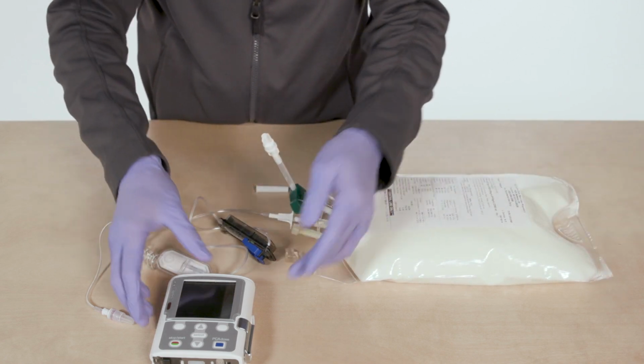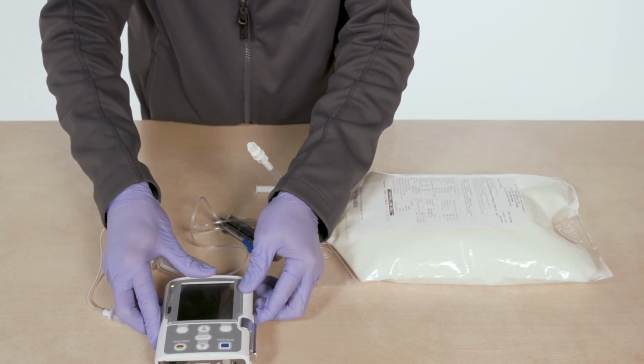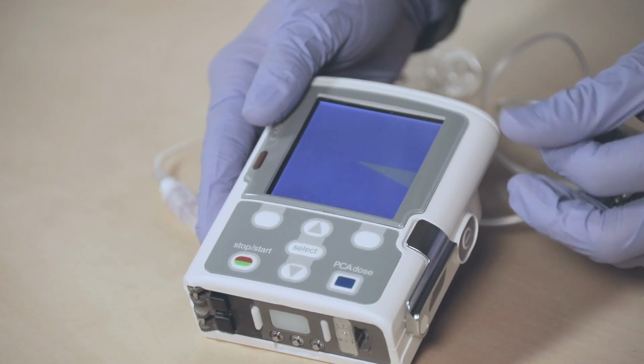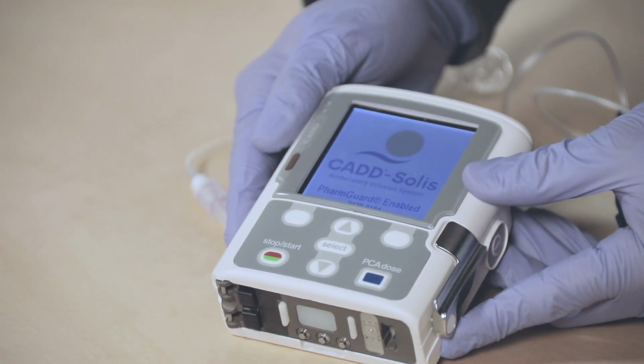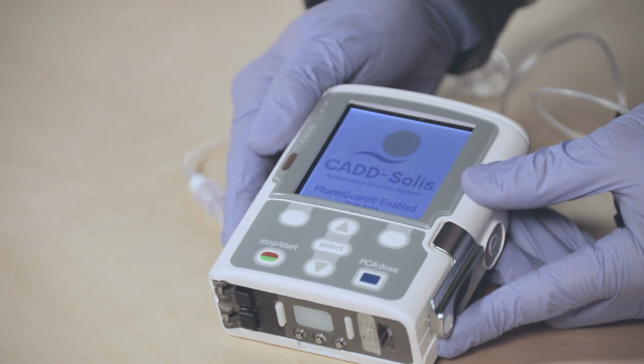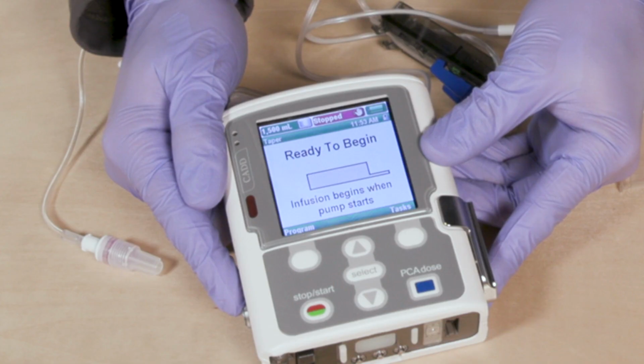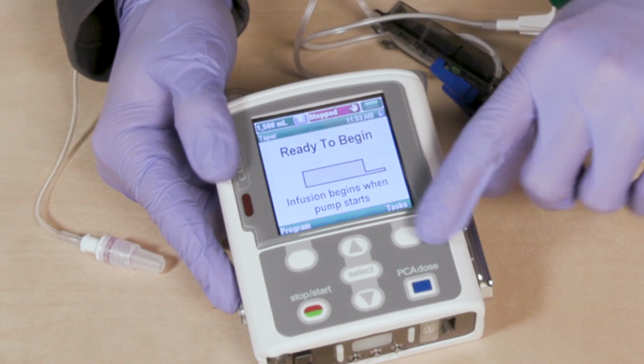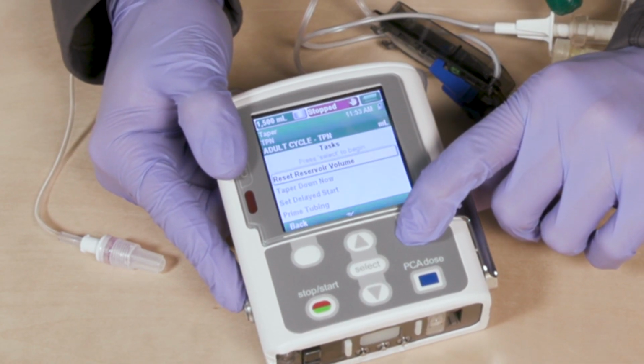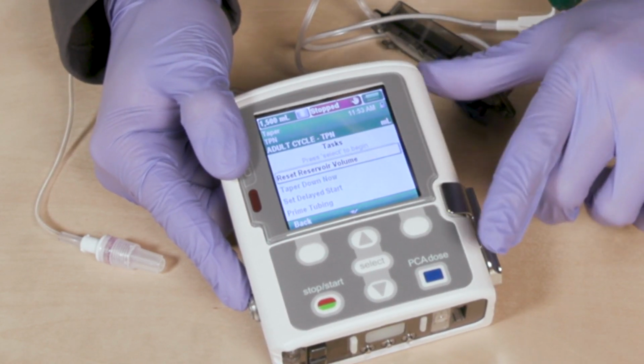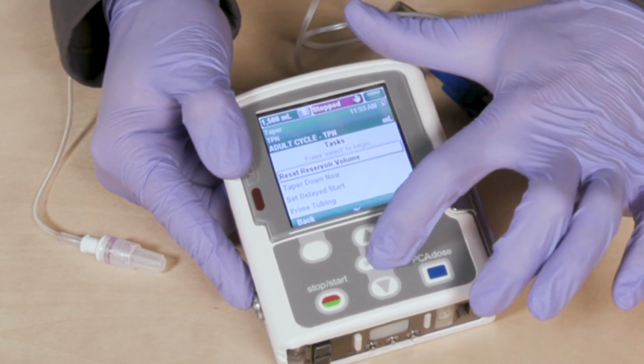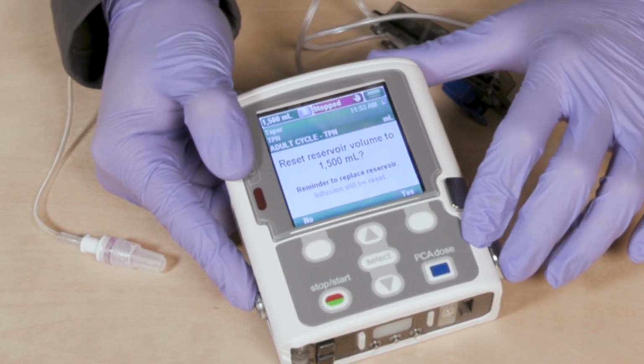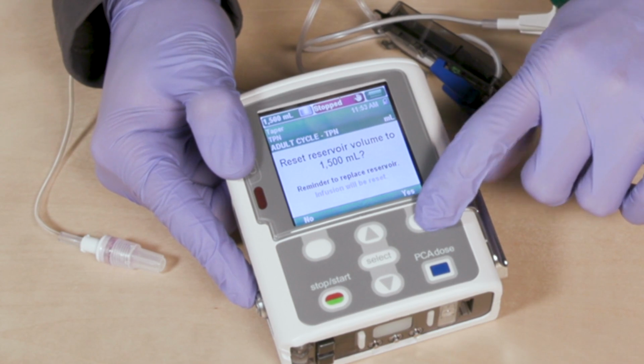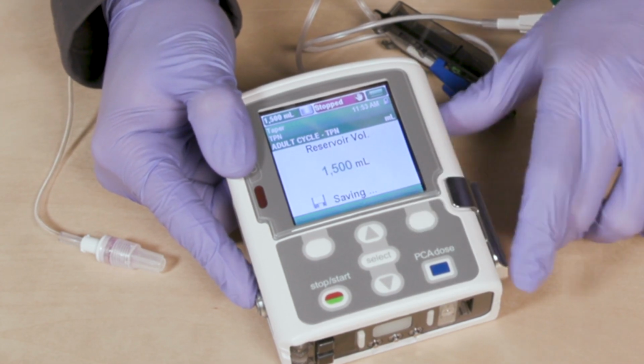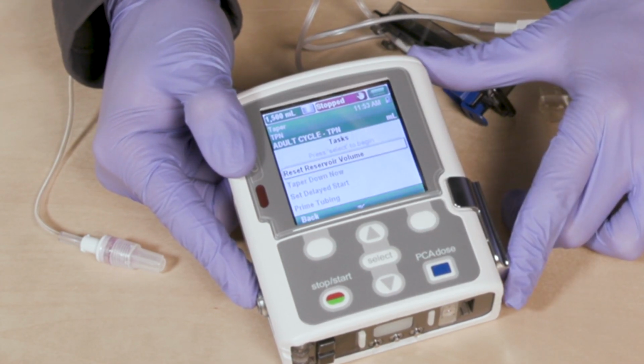Next, push the power button on the right side of the pump to turn the pump on. The pump will sound a series of 6 audible tones that signify the startup check was successful. With the pump powered on, select Task. Then select Reset Reservoir Volume. The screen will display the reservoir volume to be reset. Select Yes. Now, obtain your bag or cassette of medication.